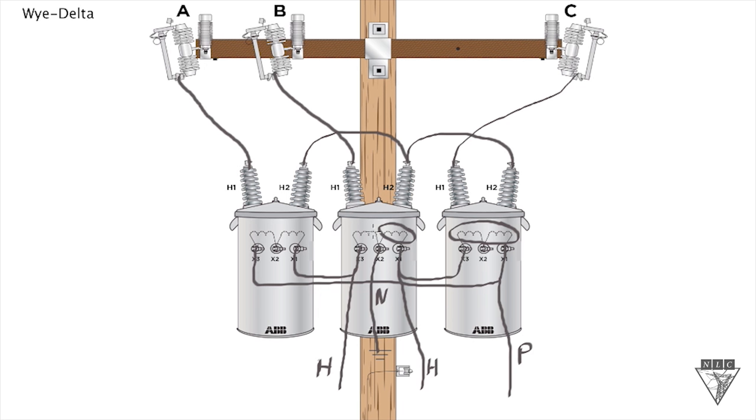On the secondary side, an advantage is if you lose power in one transformer, for temporary purposes you can just hook up two transformers and still serve power with a single phase and three phase. The one thing you have to keep in mind is it's only 57.7 percent is efficient, so it should only be for a temporary use.